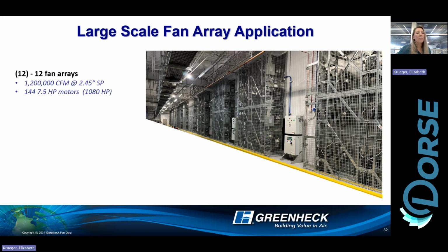So beyond, I know I've been really hitting on the air handling units, but we do supply these same MOAs for large scale fan array applications as well. This is just an example. Each of these is a 12 fan array. We can actually go double the height with these now. We can stack these fans 8 high and as many wide as you need. This one's doing 1.2 million CFM with 144 fans. So pretty neat, pretty intense application there.